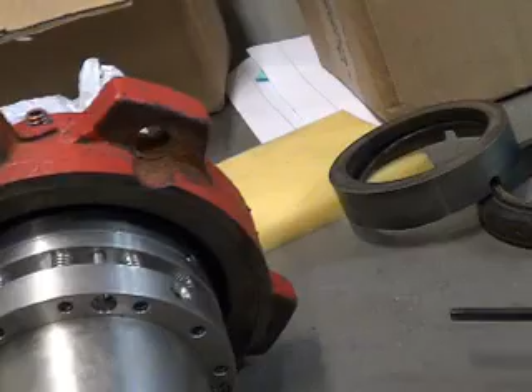Okay, so I've got to push down like that. What we did is line up the two holes on the sleeve with the two set screws on the collar. I bottomed those out. They don't protrude past the sleeve. Our new seal is now assembled as a cartridge, and we've got contact, we've got sealing, and everything's tight.